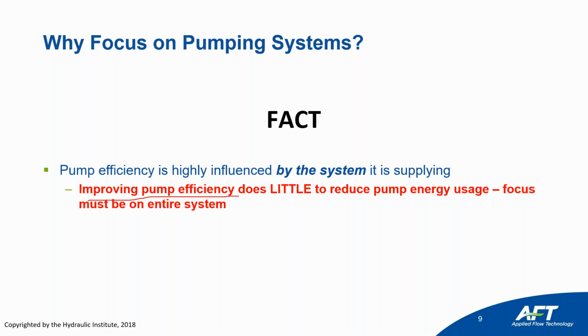Do you have a lot of valves in your system? Are they throttled? Do you have a lot of flow paths that are turned on which may not need to be on? Maybe you're running too many pumps at a time. Maybe you're running 5 pumps when you only need to run 2. Okay, and so it's not just about focusing on the efficiency of the pump itself by putting a VSD on there. It's about focusing on the system as a whole, and that's why doing flow analysis is really helpful because it gives you a much better picture of what's going on in the whole system.